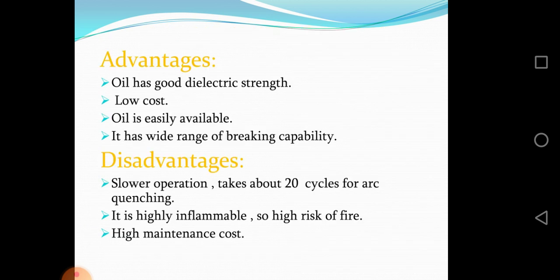Advantages: oil has good dielectric strength, low cost — oil circuit breakers are cheap and oil is easily available — and a wide range of breaking capability. Disadvantages: slower operation, taking about 20 cycles for arc quenching; it is highly inflammable so there is a high risk of fire; and high maintenance cost.